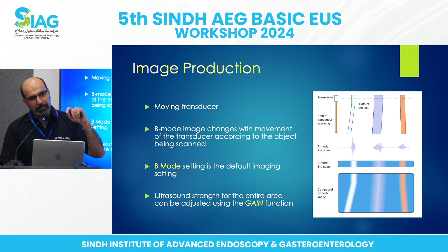You also have fine-tuning, just like in anything else. You have the big dial on the bigger machines for the overall image gain, and then you have these fine-tuning measurement controls, which are basically distance from the probe. If you look on the right side, each little knob here is a certain depth from the probe. So if you want to fine-tune a certain image because you're getting artifacts, say close to the tip of the probe, then you can adjust this.